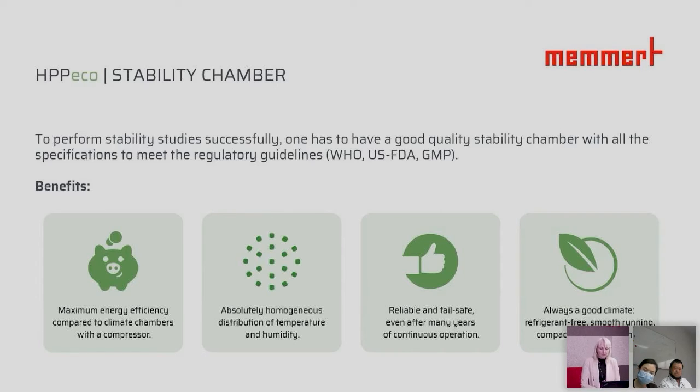It is very important to have absolutely homogeneous distribution inside in regard to temperature and humidity. It must be reliable and fail-safe because we're talking about this testing, which takes a really long period of time. So of course, it is important that you have a safe product. And always a good climate, refrigerant-free, smooth-running, compact, low maintenance.